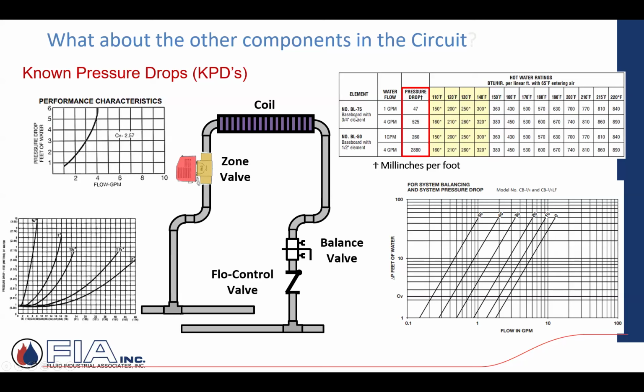I have this baseboard. Well, I have this literature from the manufacturer that tells me the pressure drop. I have a balancing valve. I have a performance chart that says what the pressure drop is. So I have all of these pieces of literature that list out the various pressure drops for the control valve, the terminal unit, the balance, the flow control, or the check valve. You've got to account for that. So in addition to the piping, which is very important, now what else am I putting it through? And these manufacturers will list or have these known pressure drops listed, rated.